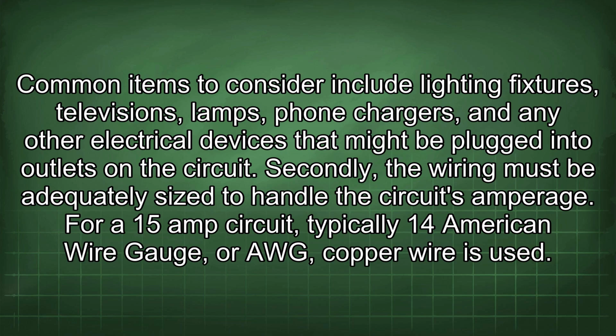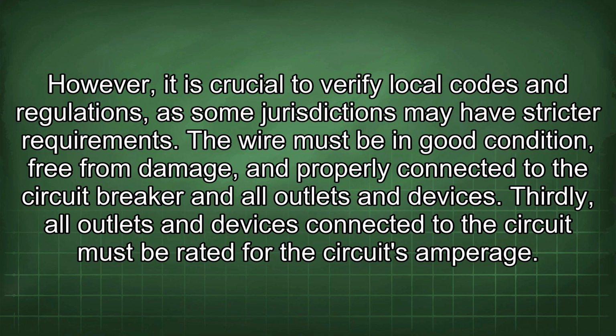Secondly, the wiring must be adequately sized to handle the circuit's amperage. For a 15 amp circuit, typically 14 American wire gauge, or AWG, copper wire is used. However, it is crucial to verify local codes and regulations, as some jurisdictions may have stricter requirements. The wire must be in good condition, free from damage, and properly connected to the circuit breaker, all outlets and devices. Thirdly, all outlets and devices connected to the circuit must be rated for the circuit's amperage.